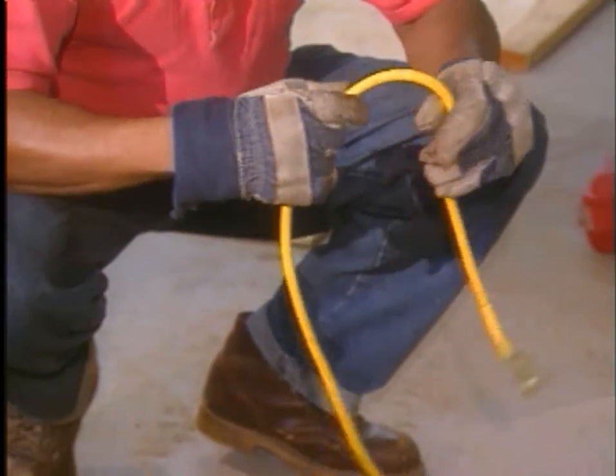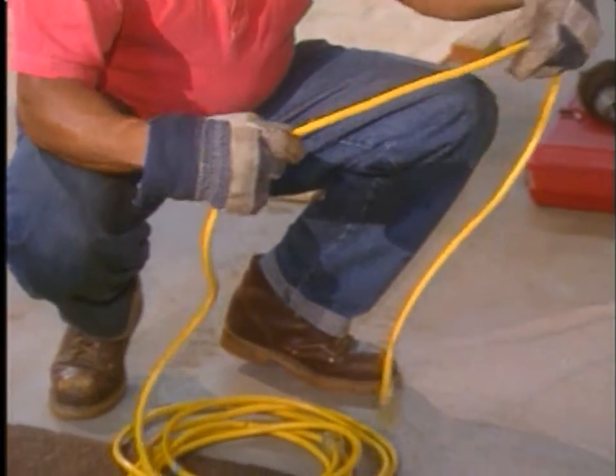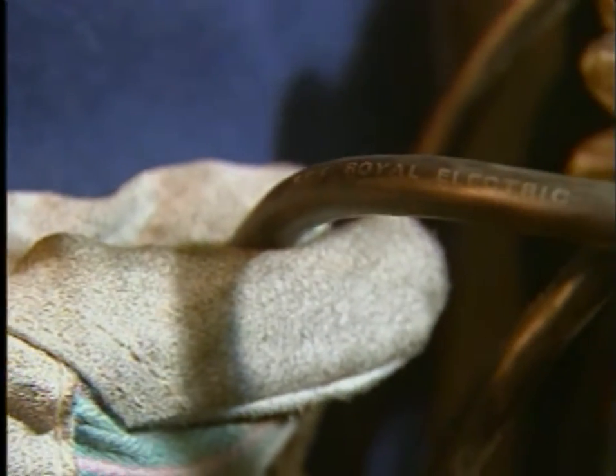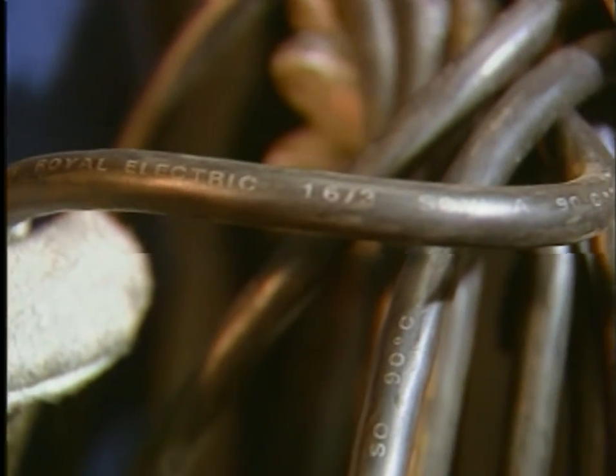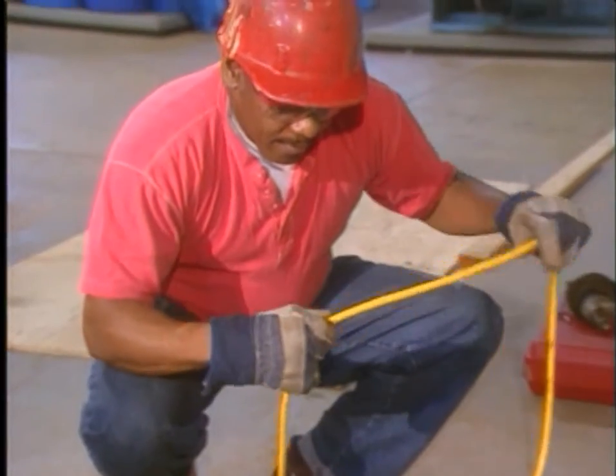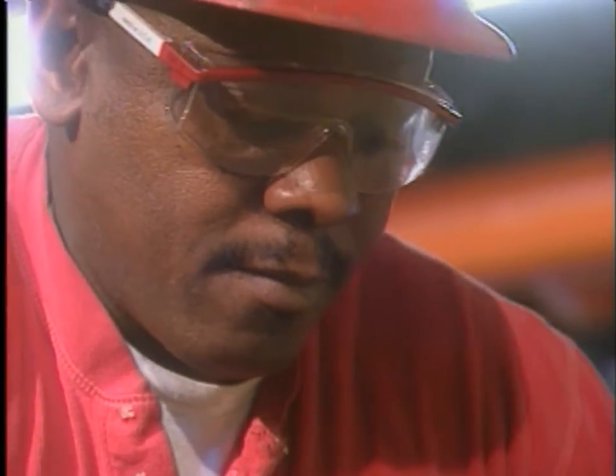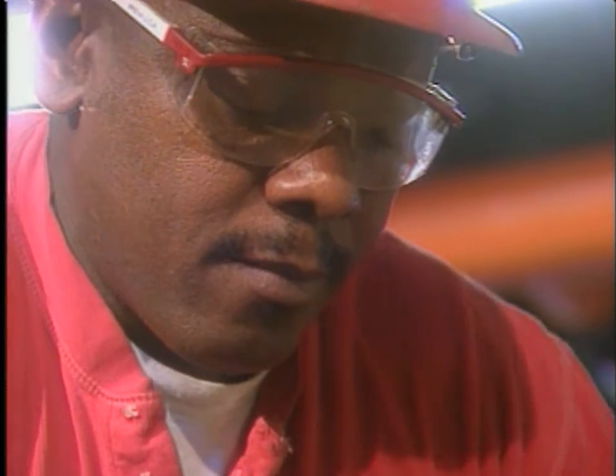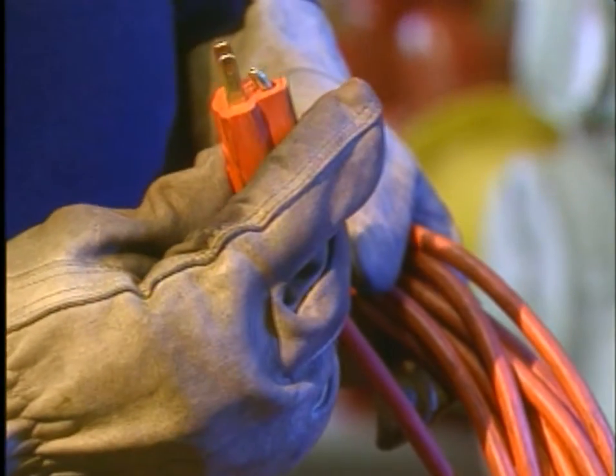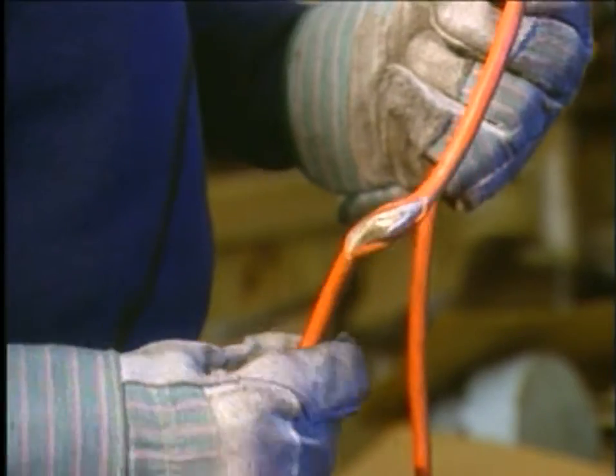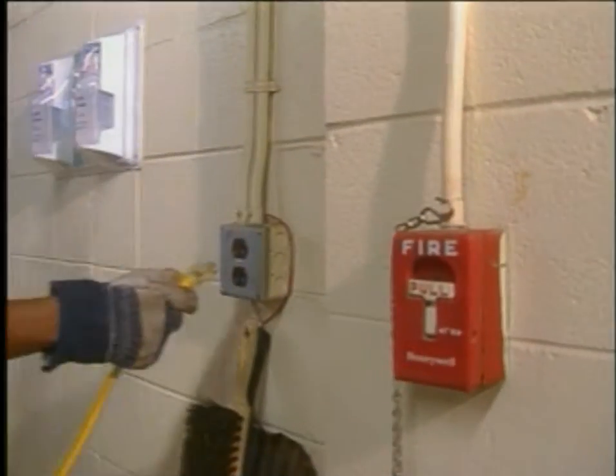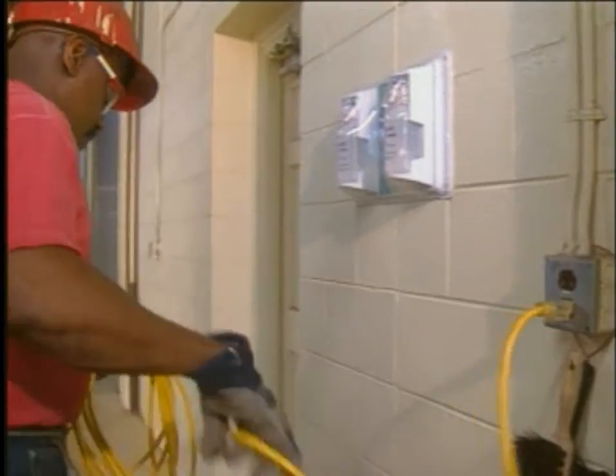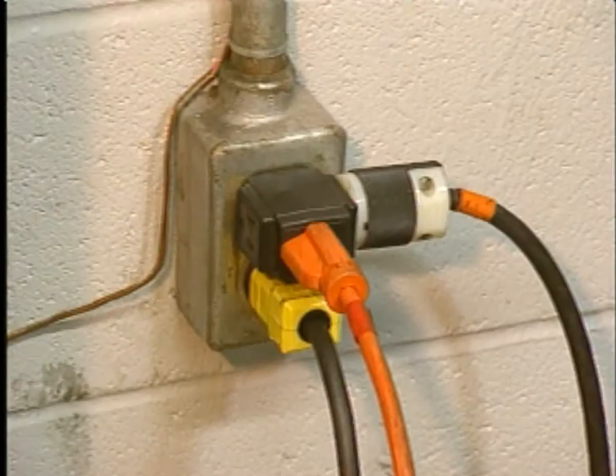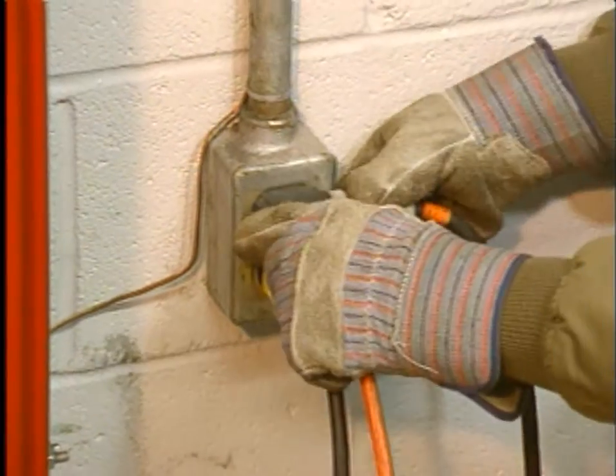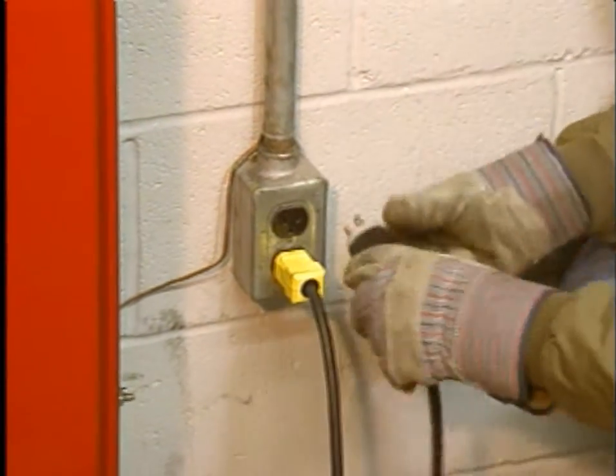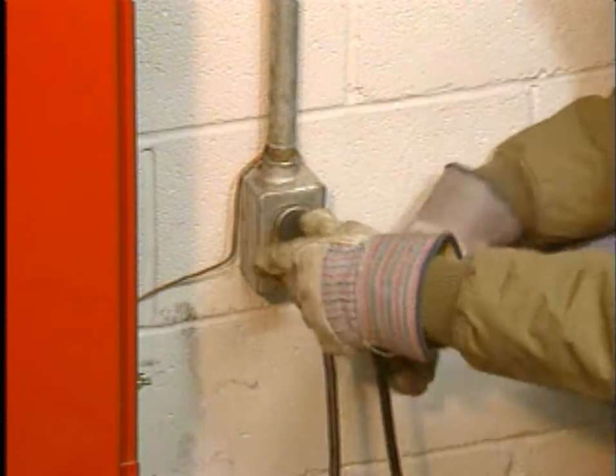Unsafe portable electric extension cords are common causes of electrical shock. That's why it's important to be sure the one you use on the job is rated for the job. Before your shift begins, inspect any portable extension cord you might use for loose parts, deformed and missing pins, or damage to its outer jacket or insulation. Be sure its plug and the receptacle are designed to be used together. Safe outlets are grounded and should never be overloaded. More than 2 plugs per double outlet is overloaded.